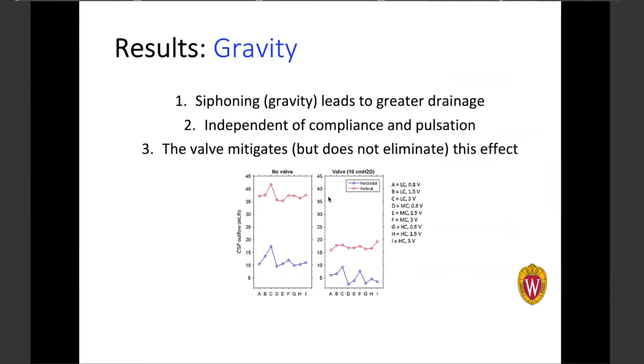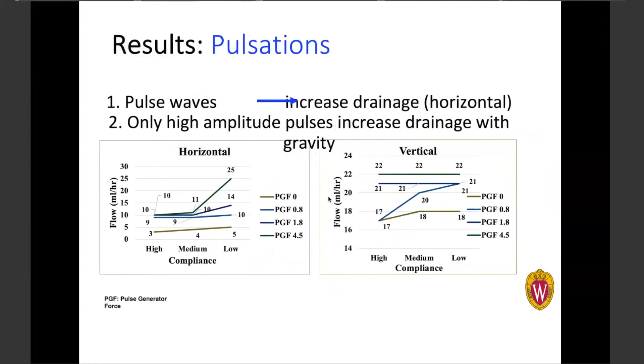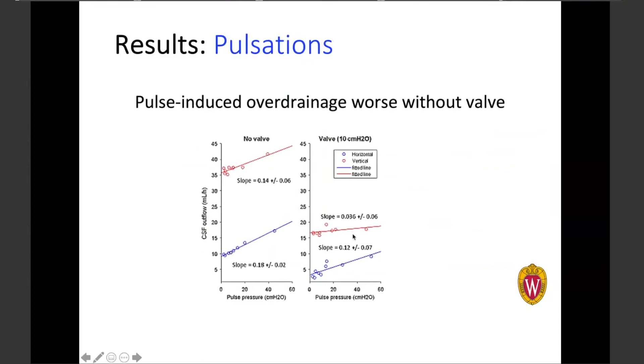Second, when we add pulsations into the system, we found that indeed in the horizontal position, every pulse wave further increases drainage through the shunt system. And that's, of course, mainly in the horizontal position. In the vertical position, gravity is so substantial that it overwhelms the effect of the pulse wave. Then, when we added a valve into the system, it decreases the effects of these pulsations, but again, it did not eliminate them. You still have quite a bit of overdrainage compared to expected.